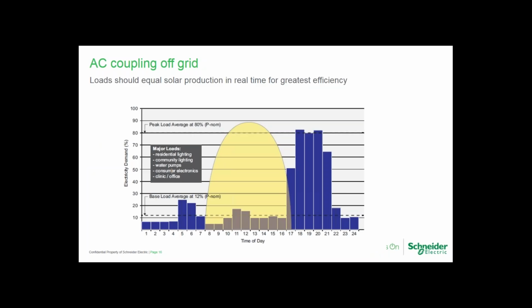So here's a chart, and this goes to the question of efficiency. A lot of people say you just get much better efficiency when you're AC coupling. Well, that's true under certain conditions. Here we see an example of a real load profile. We don't know the state of charge in the battery when the day started, nor the capacity. This is just related to load and PV availability. Most of the load demand is occurring outside of solar hours, so this does not allow you to gain any advantage when you're AC coupling.